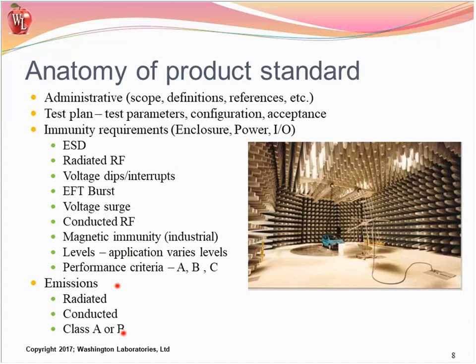Just to help with the identification, performance criteria A indicates that it needs to operate during events. In other words, ESD cannot cause it to go away and have to reboot or restore operation with operator. B says it can go away temporarily, but will restore operation with no loss of data. So it needs to come back to life.